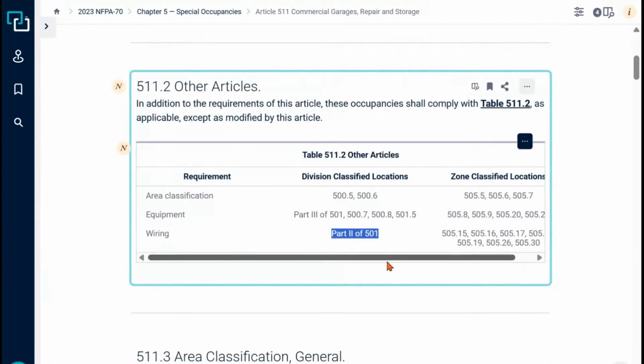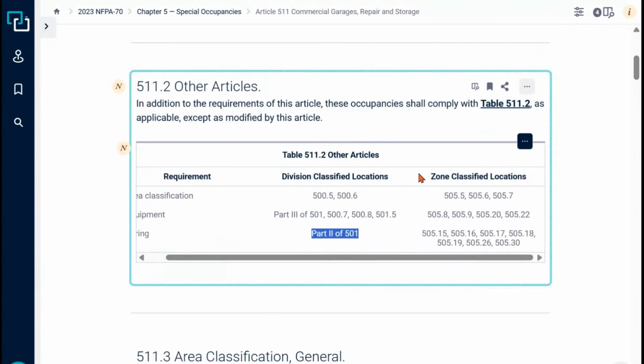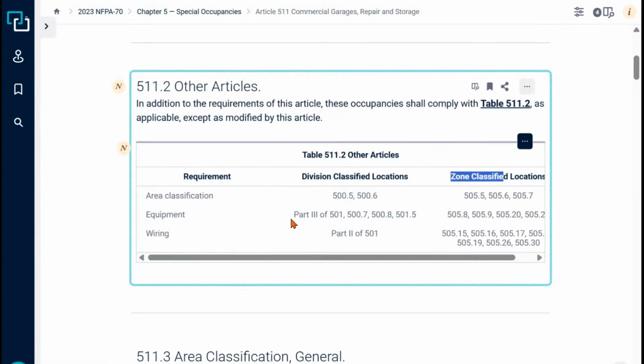501, we know that is Class 1 locations, right? And it's also going to tell you the same equivalent if you're using the zone system. You can use either the zones or the division—it's up to you. Mostly in Europe they use zone; in the US, or North America, we tend to use division. But again, they kind of overlap. We'll go over some of that in upcoming episodes—a video or coffee hour that explains the zones in comparison to the division. Your engineer can use either; it's not a problem.